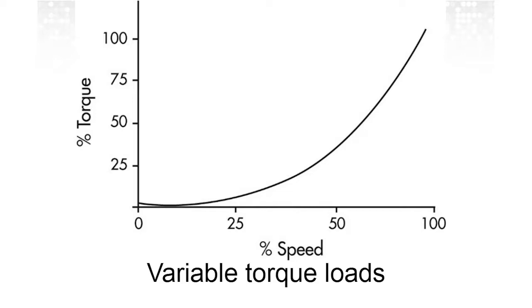So we can now look at these various torque curves. This is a variable torque load of percent torque versus percent speed. If you notice, it goes up sort of as an ellipse or part of an ellipse. And that shows you this is a square law curve showing the reduction. As you can see, at 50% speed, you're at about 25% torque. And of course, at 25% speed, you're down here at 10% torque.